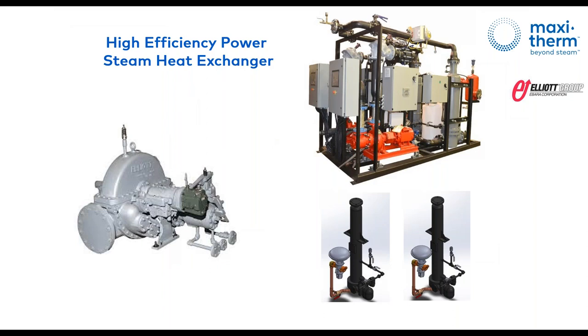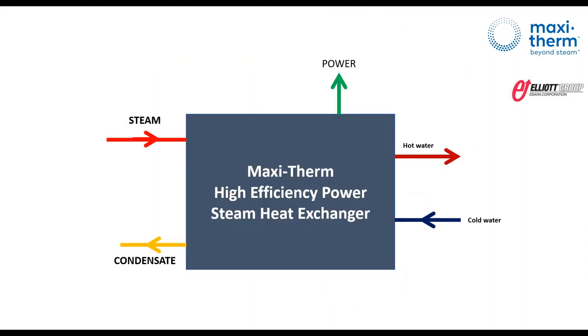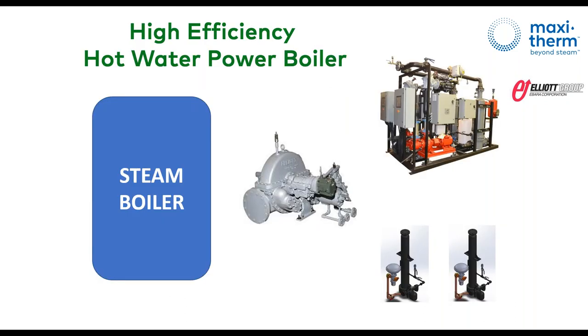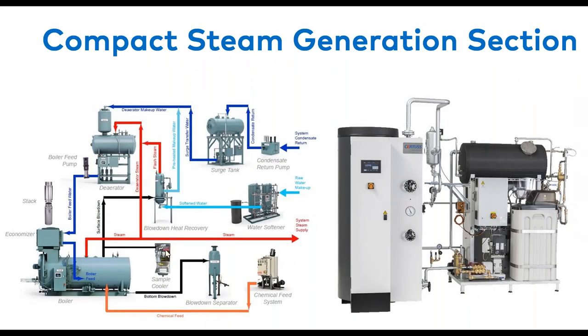So we can do a full skid package with Elliott for building heat, reheat, whatever process you want to install. It will be only 5 connections for the main contractors: steam inlet, condensate outlet, cold water, hot water, and power. We were thinking also of offering a complete steam boiler room that generates power and hot water. So it becomes a high efficiency hot water power boiler, right? Those types of boilers are really great boilers, don't get me wrong, but they take a lot of room. There's a new generation, which we call the coil type, really more compact, about 4x less footprint.